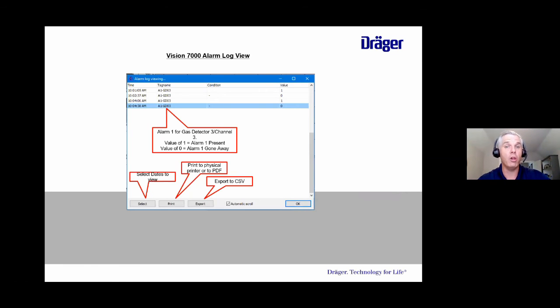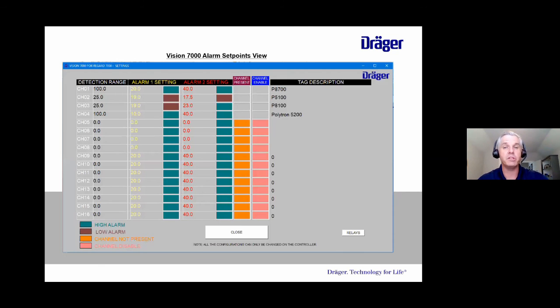This is basically the alarm log view. If you hit the alarm log button on the front screen, it will show you the alarm history for all the channel inputs. You can print it, or you can export that to a CSV file and look at all that data in Excel. This is basically your alarm set point view. You can look at all the different alarm set points and where they're at.